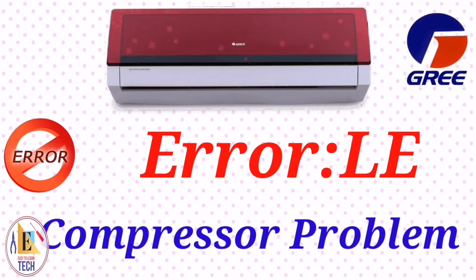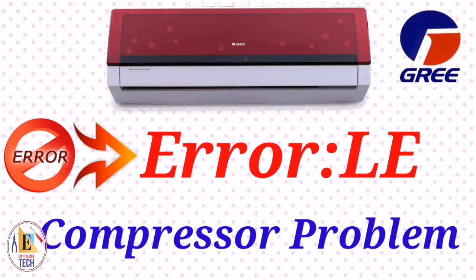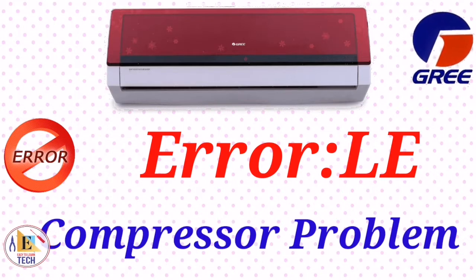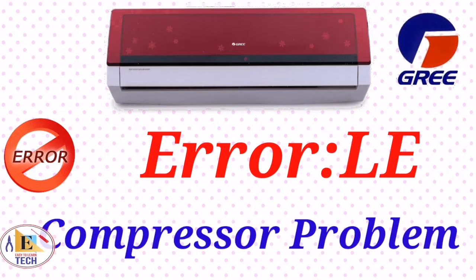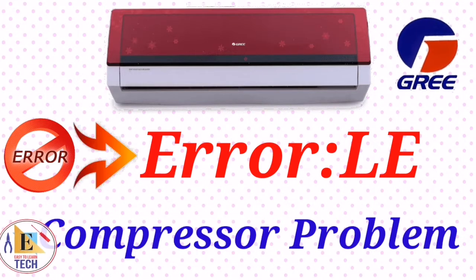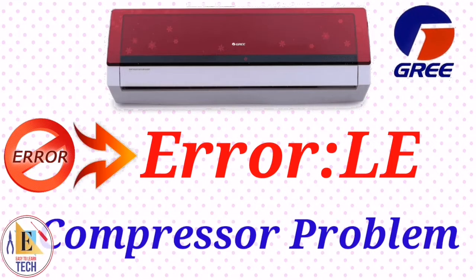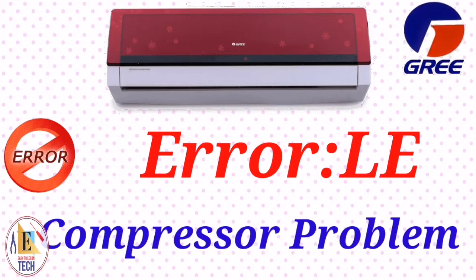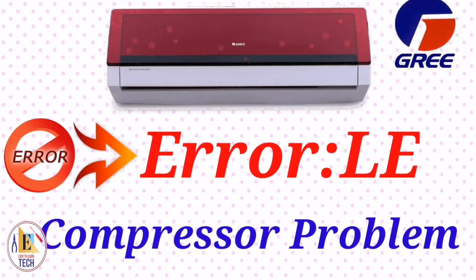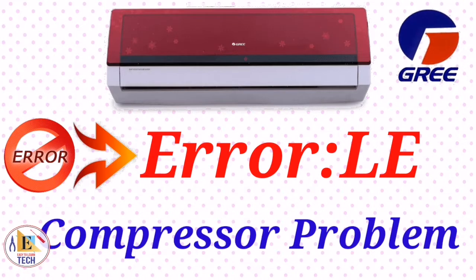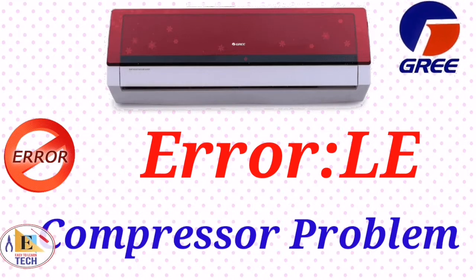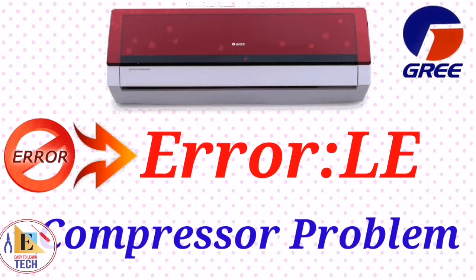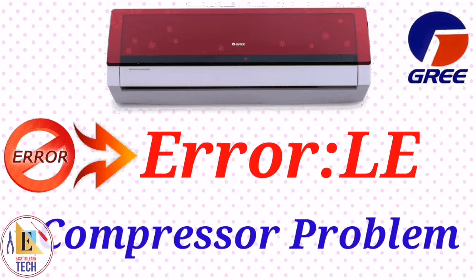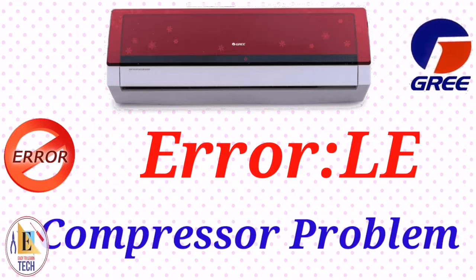And again, if you get the same error, then you have to check the compressor, then you have to check the terminal of our compressor if it is burned or something like that. If it is not burned, then you have to check the continuity, then you have to check the ground of our compressor. And if you find our compressor is okay, then you have to check the outdoor PCB, if the power supply which is coming from our outdoor PCB is okay or not. If the power supply which is coming from the outdoor PCB is not perfect, then you have to change the outdoor PCB and our unit will be working.